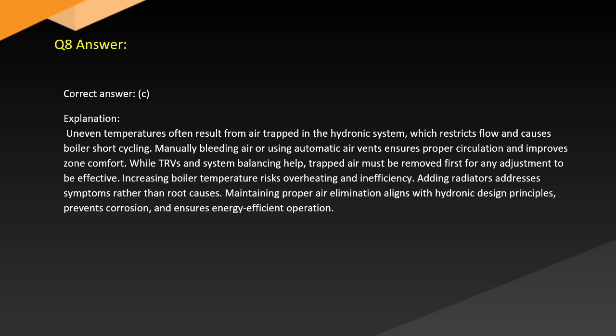Increasing boiler temperature risks overheating and inefficiency. Adding radiators addresses symptoms rather than root causes. Maintaining proper air elimination aligns with hydronic design principles, prevents corrosion, and ensures energy-efficient operation.